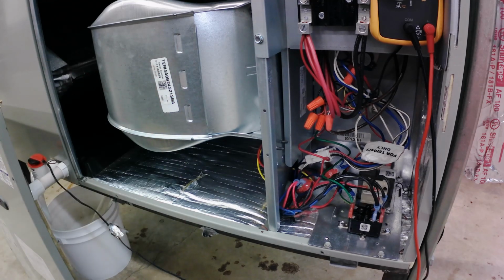So if you have a PSC motor and the motor's not working and you verified low voltage to the coil, you verified voltage in and out of the relay switch, you may want to check your capacitor and then the motor. But a lot of people here lately have been blaming relays or capacitors or bad motors without troubleshooting, and this is just a snapshot of troubleshooting it. So I hope it makes a little sense to you. There's a couple guys that I'm trying to get this across to really, and I know that they'll probably watch this. So let me go check a contactor, and that'll be the last thing, and then we'll be done.